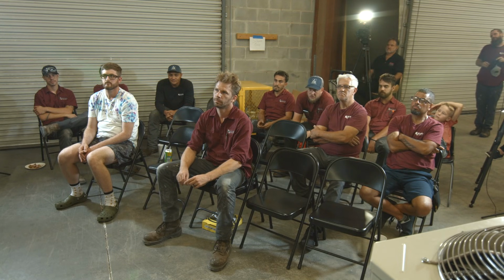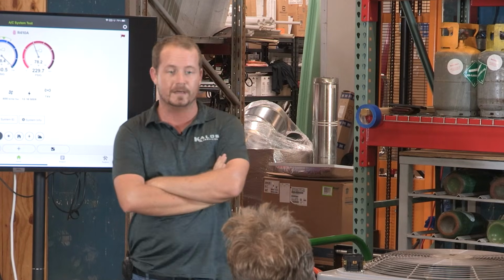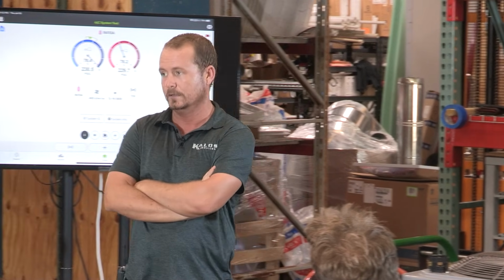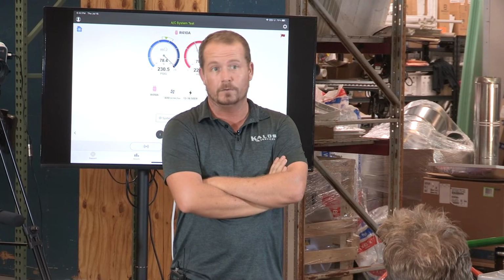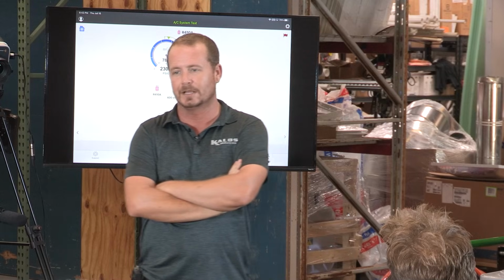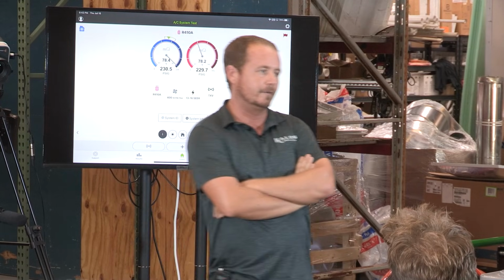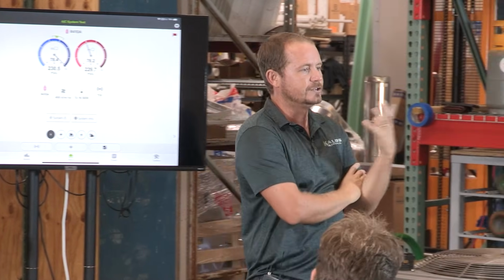On a lot of systems, it's going to drop a lot because that's a programming feature. If you have a cool call without a G call, on a lot of systems, not all, it's going to produce lower airflow. And again, I beat these drums a lot. I cover this a lot, but there's a lot of things you've got to check.